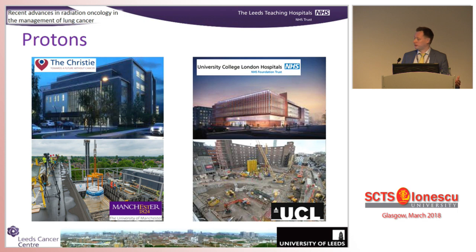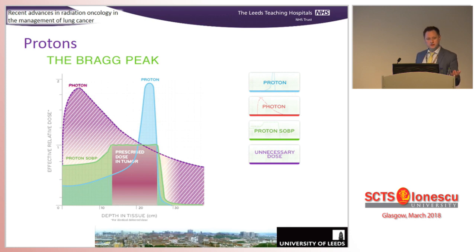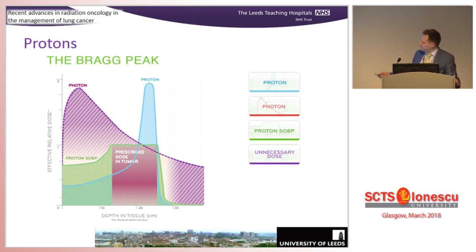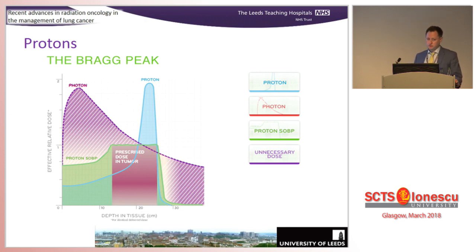Why are protons so expensive - each centre costs about 150 million pounds - but also why are they potentially advantageous? Our standard beam is a photon beam: as it hits the patient, the maximum dose is usually around one and a half to two centimetres underneath the skin, and that dose falls as you go towards the tumour, so we have to use lots of beams. But protons have a property called the Bragg peak - they're a heavy particle, they go through the body, and when they get to a certain depth they deposit their energy very quickly, then the energy falls off very rapidly afterwards, giving a very steep dose gradient between tumour and normal tissue.